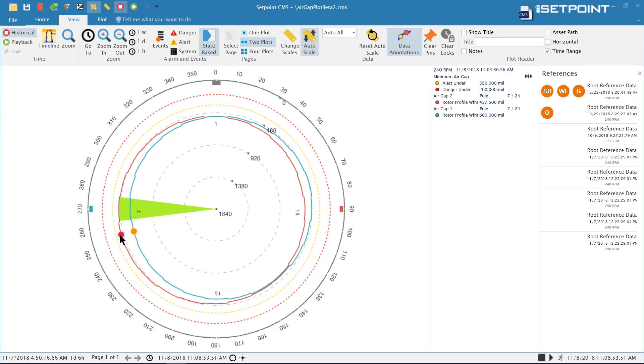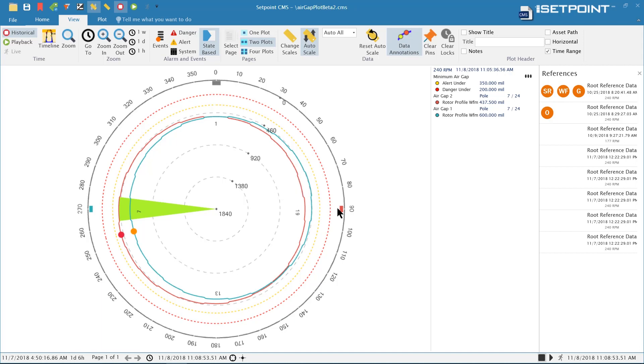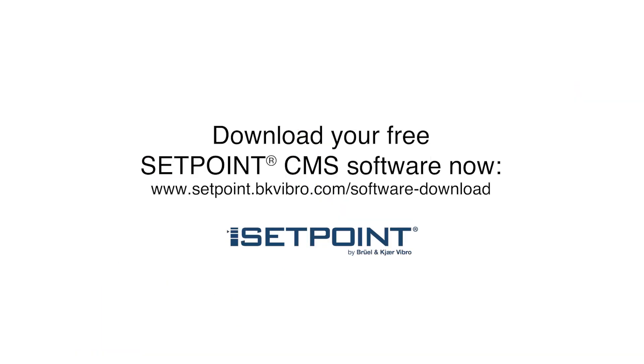The data identifies the minimum and maximum pole space on the gap, so you can tell at a glance which section has the tightest clearance and where it is on the turbine. It also identifies where the sensors are on the turbine so you can tell the relationship of everything, as well as where the phase trigger is located. That's the air gap plot and that's a basic overview of the features that have been added to the new version of Setpoint CMS. Please visit our website to download the latest version of Setpoint CMS. We look forward to working with you in the future.